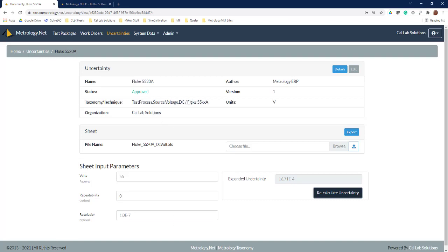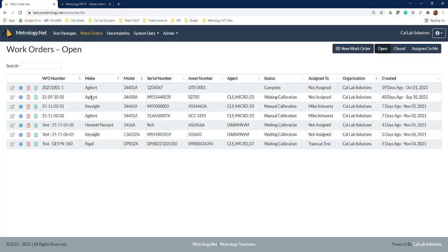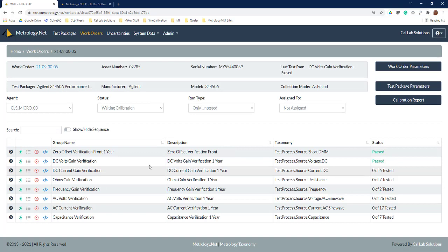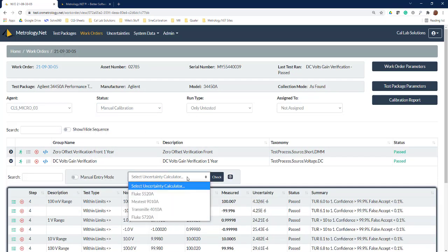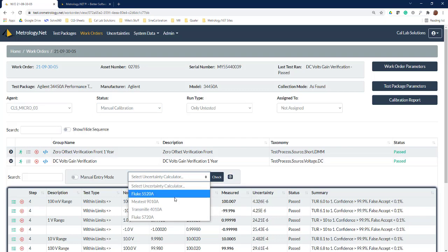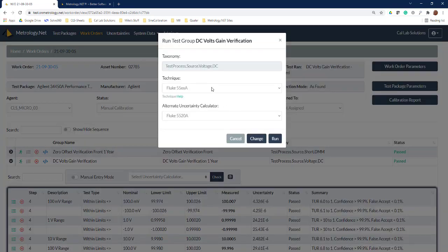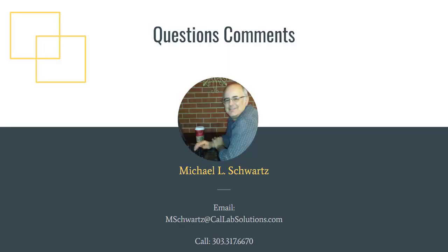Now we'll jump back here real quick and you can see that when we edited this, we applied this to our test process source volts DC 5500. So now when we come back in here and look at our work order, you can see that this is a taxonomy of test process source volts DC. When we set this into a manual calibration mode, it pulls all of those calculators we have associated with source volts DC and puts them in here. When we want to run the calibration, this is tying this measurement uncertainty to the source volts DC 5500 technique. This allows us to get the automation very specifically tied to the measurement process that we're using inside of our software.